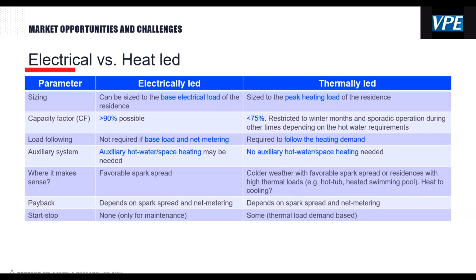Now, if you are sizing your CHP system to the peak heating load of the residence, it's going to satisfy all your heating demand, be it hot water or space heating. However, the electricity that is produced is a byproduct. You produce what you produce when you produce, depending on when the CHP system is on to satisfy the heating needs. So in that case, there's no auxiliary hot water or space heating needed, but the electricity produced is just a byproduct.